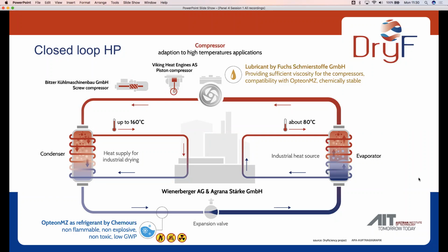We have a lubricant specialist within the team, Fuchs Schmierstoffe, and they developed a lubricant that is compatible with the refrigerant, and it's supposed to be stable at the high operation temperatures. As the refrigerant, we use Opteon MZ from Chemours. It's a synthetic material, R1336MZZ(Z), which has a low GWP value, which is very important to come up with an environmentally friendly solution.